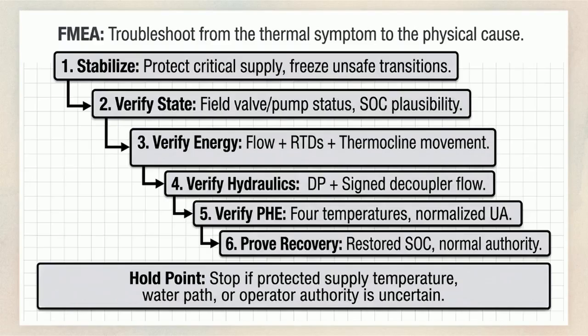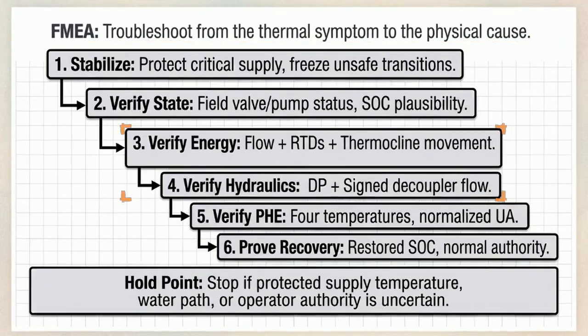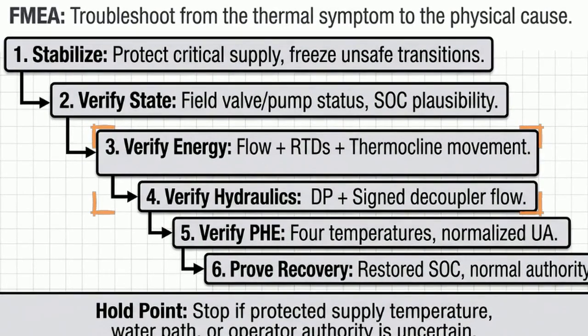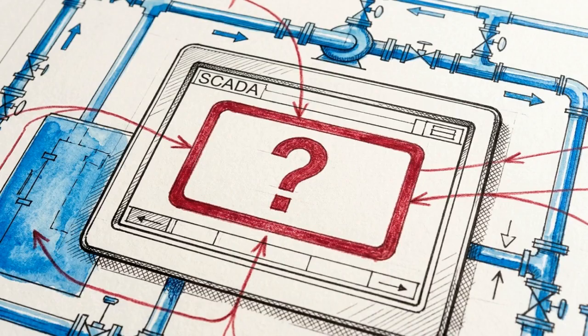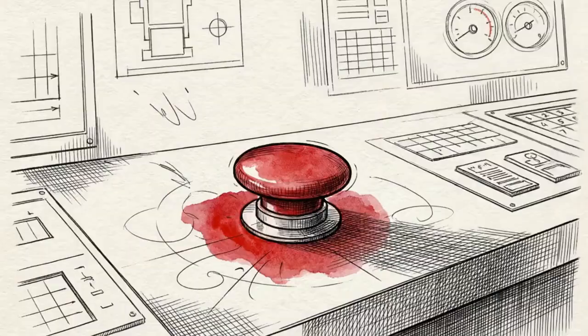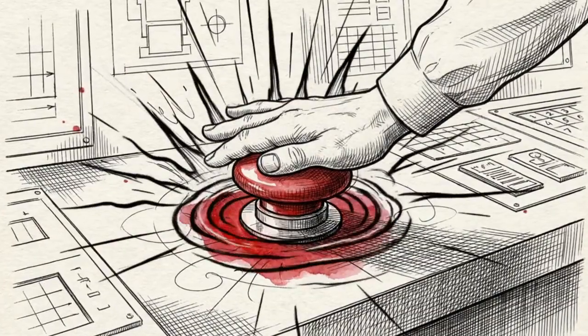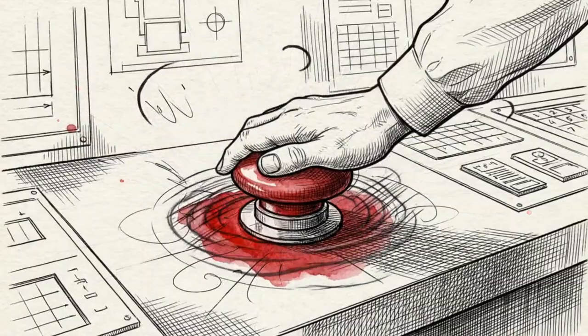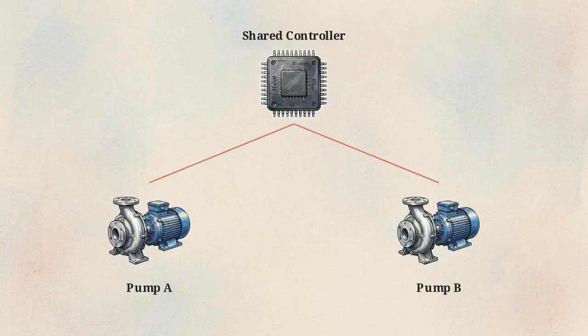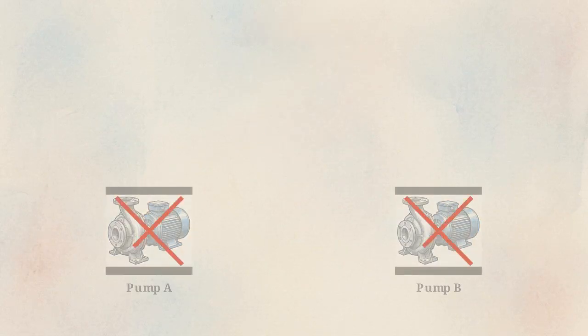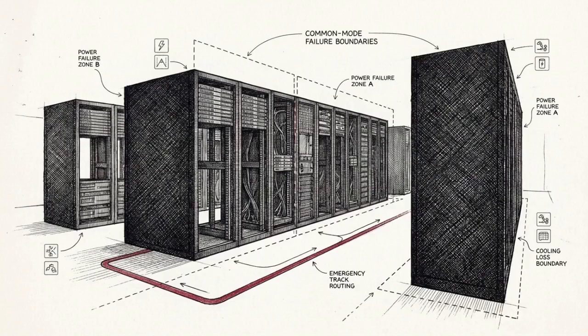When a test fails, engineers execute a failure mode and effects analysis to troubleshoot from the thermal symptom back to the physical cause. Steps 3 and 4 are critical here, verifying the thermal energy data and then verifying the hydraulic flow and pressure. For example, if the header supply temperature is uncertain or the water path is unverified, the operator must immediately stop and execute the abnormal path fallback sequence to protect the load. Troubleshooting often reveals that architectural redundancy is an illusion if parallel equipment shares a single sensor array or controller. These single points of failure act as common mode hold points that can bring down the entire plant.